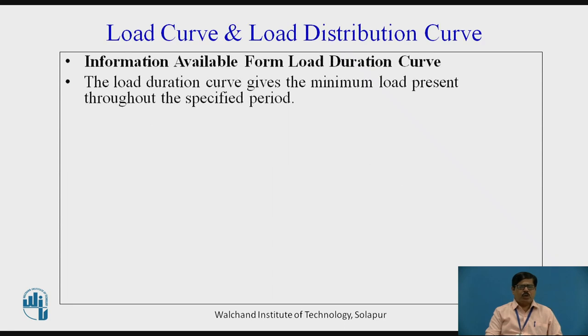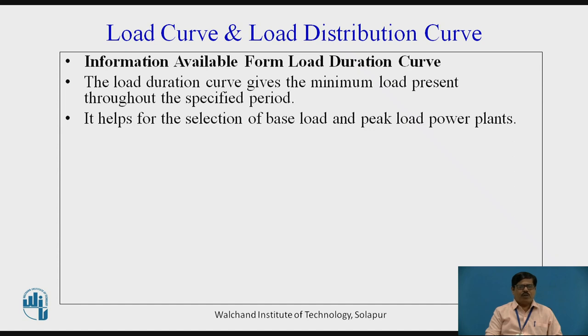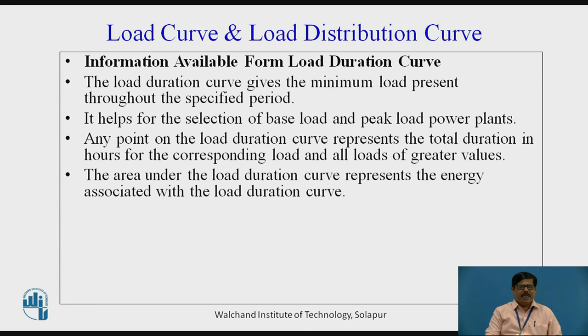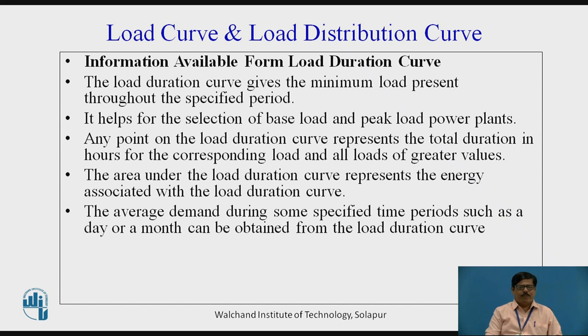Now, what information do we get from the Load Duration Curve? The Load Duration Curve gives the minimum load present throughout the specified period. It helps in the selection of base load and peak load power plants. When the load is almost uniform and constant, we can run the base load plant. But if the load exceeds the average or minimum required load, then we have to operate the peak load plant for that particular period. Any point on the Load Duration Curve represents the total duration in hours for the corresponding load and all loads of greater value. The area under the Load Duration Curve represents the energy associated with the load duration. The average demand during a specified time period such as a day or month can also be obtained from the Load Duration Curve.